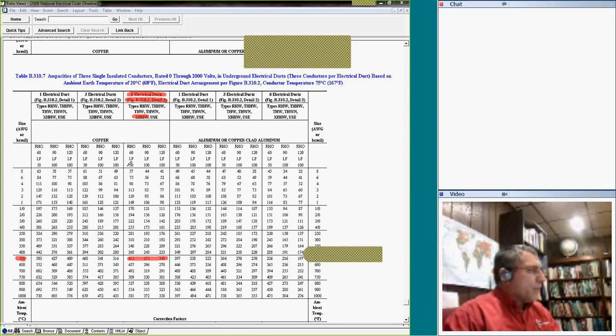So which one am I going to be choosing? Based on the resistivity of the earth, guys, and there's software that can identify this one. If you don't know, usually you default to that one, and the load factor of 100%. That's your default, unless you know otherwise. At least my default. And based on that, 500 kcmil, beautiful 500 kcmil, can carry only 273 amps.